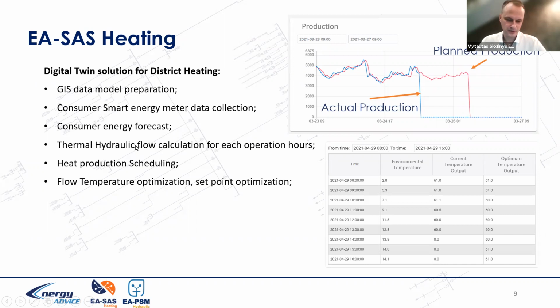But our thermal hydraulic calculation is focused on optimization of the performance of a grid. And finally, you have heat production scheduling, and flow temperature optimization, as a set point, is delivered to the control room. Here you see an example at the control room side: the environmental temperature forecasted each hour. You see here existing, and here forecasted, with current temperature output and optimum temperature output to the district heating network. Here you can see interesting numbers, 60 degrees. It's in the month of April, at the end of April, and yes, this is correct data, and the district heating company operates on such a level of temperatures.